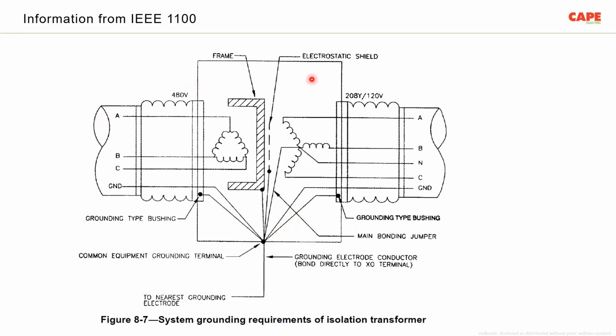That is the earthing. Now, here is a picture I took from IEEE 1100. You can see the ground wire coming in is connected to a common point. The frame is connected to the common point. The electrostatic shield is connected to the same point. The outgoing ground wire and the body are connected to the same point. And what you should see is that the neutral, the star point of the transformer, is also connected to the same point. So basically everything is interconnected at one common bonding point. This is the correct way of installing and using an isolation transformer. Why I explained this slide is that once we go deeper, after a few slides, you will be able to find the difference between a recommended system and the system which we use.